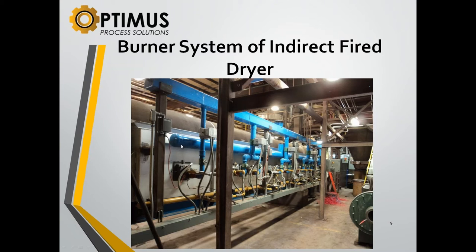Right. Okay. This is the opposite side of that dryer where you see the burners that are burning, and the top has not been placed on this one yet. But you have burners, and they are burning in zones. This is one burner that's in a zone. You have two burners here in a zone, then two more burners, and then we have a three-burner zone there, and then one. I believe that piece of equipment had nine burners on it. They have a common header for their combustion gases, but each set of burners can operate independently. So these three burners operate as one, these two operate as one, and these two operate as one. So we're monitoring the temperature of the shell, and we're firing the burners up or down, depending on the need to keep that shell at a certain temperature.